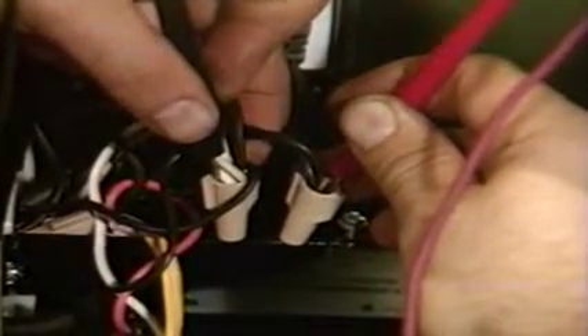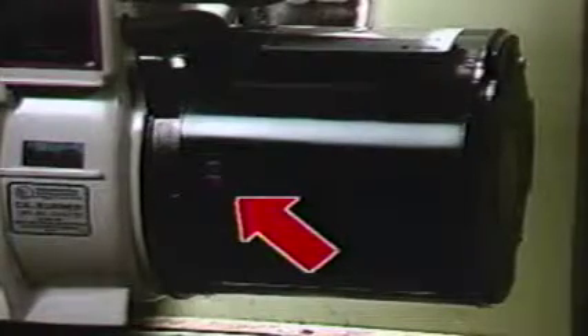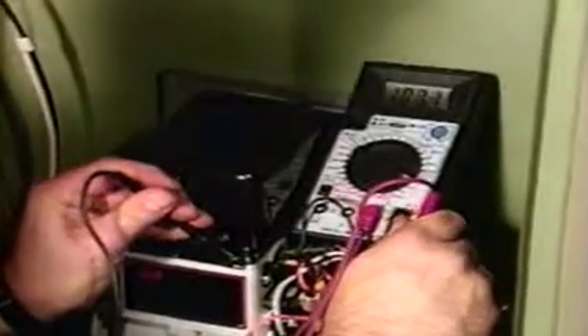If there's no motor sound at all, check for adequate voltage, or see if the overload is tripped. Measure the voltage between the motor primary lead and the neutral connection, making sure power is reaching the motor. Your reading should be within 10% of the rating on the motor nameplate. If it isn't, check the electrical input to the primary control. If it is higher than the output to the motor, then the control relay contacts or wiring are suspect.